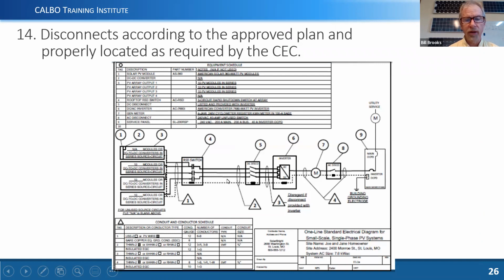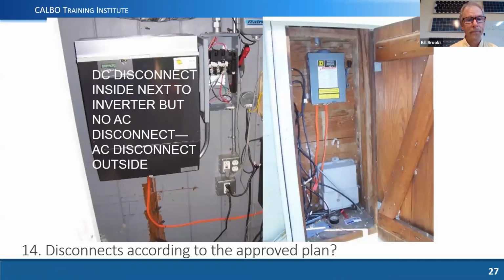Okay, and our approved plans are going to show these disconnects. This AC disconnect is being used in this particular case, and so it's called out. But a lot of times when we have a standard plan like this and we have a call out for a meter or a disconnect, it may not be used, and we just have NA under those in a standard plan arrangement.